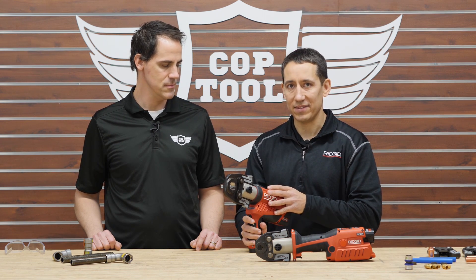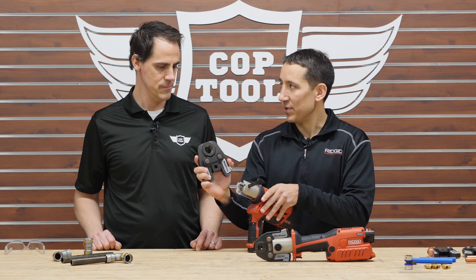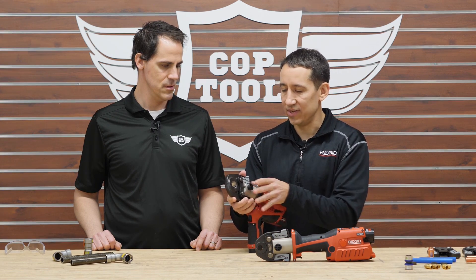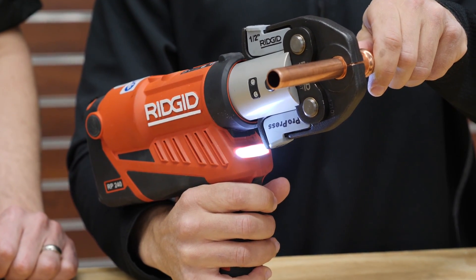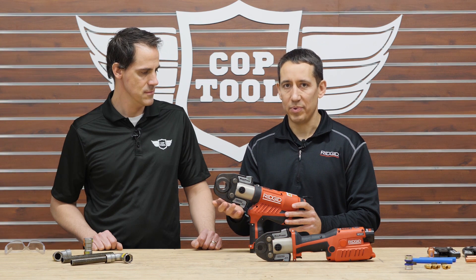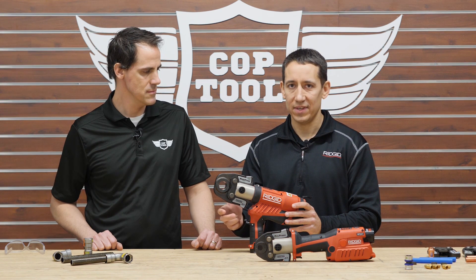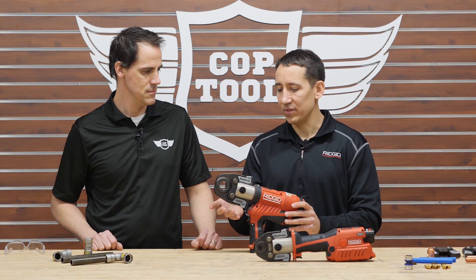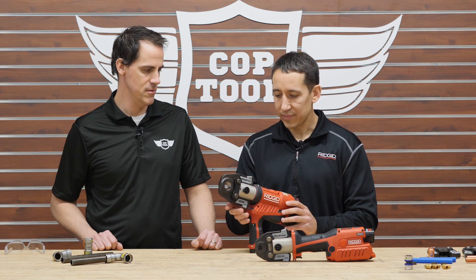Both tools have the same capabilities and capacities, using Ridgid's 24 kilonewton jaws. You can quickly swap between jaws to change sizes or systems. They work on multiple systems including copper up to 1¼ inch, black steel pipe up to ¾ inch, PEX systems — both ASTM F1807 and Viega PureFlow — up to 1½ inch, and stainless steel tubes up to 1¼ inch.